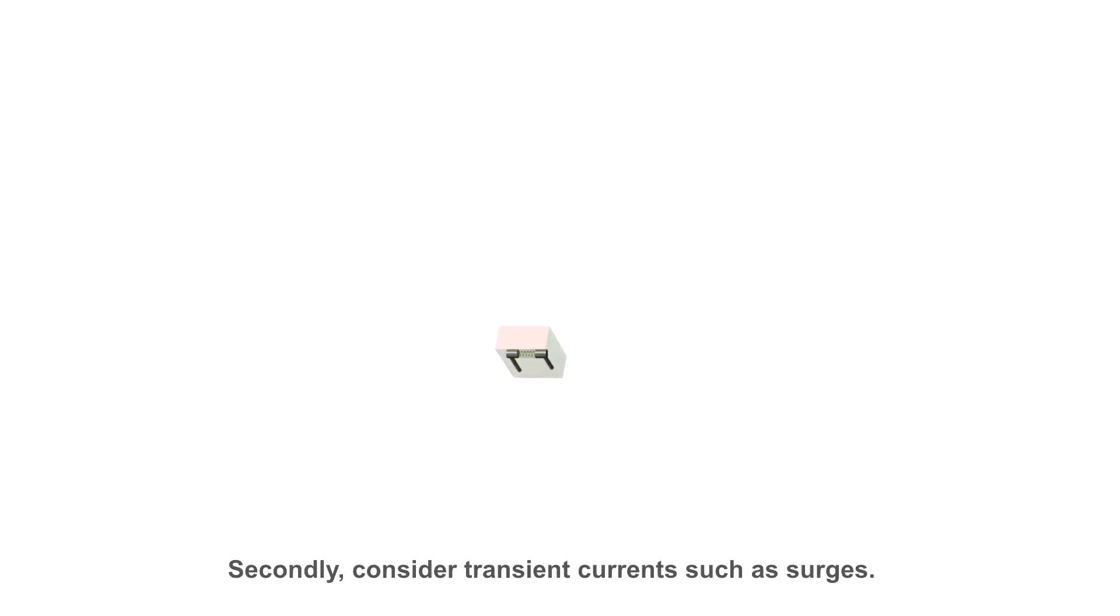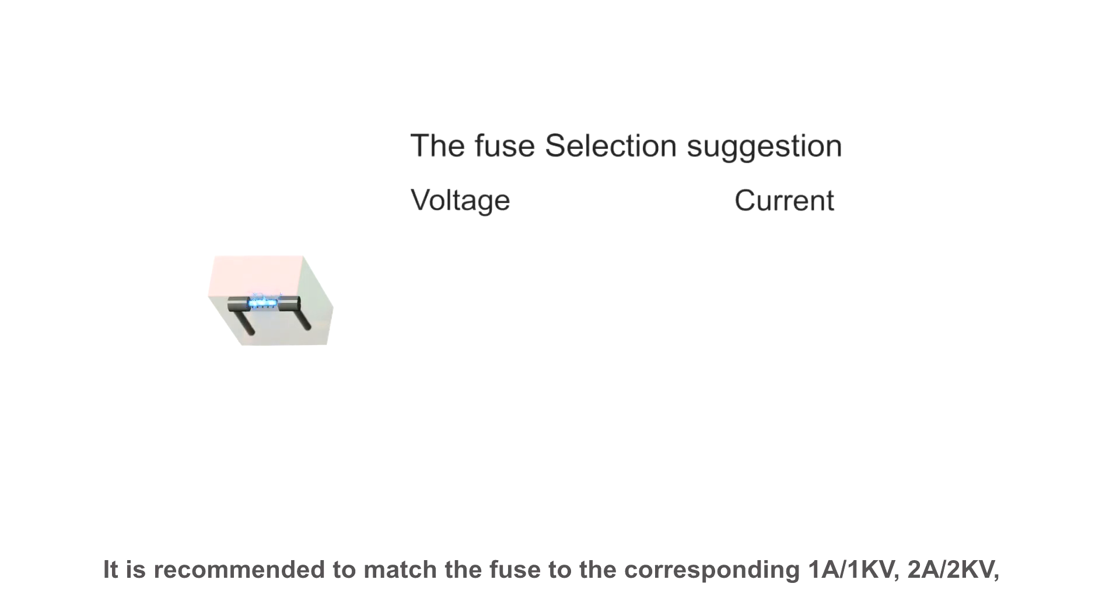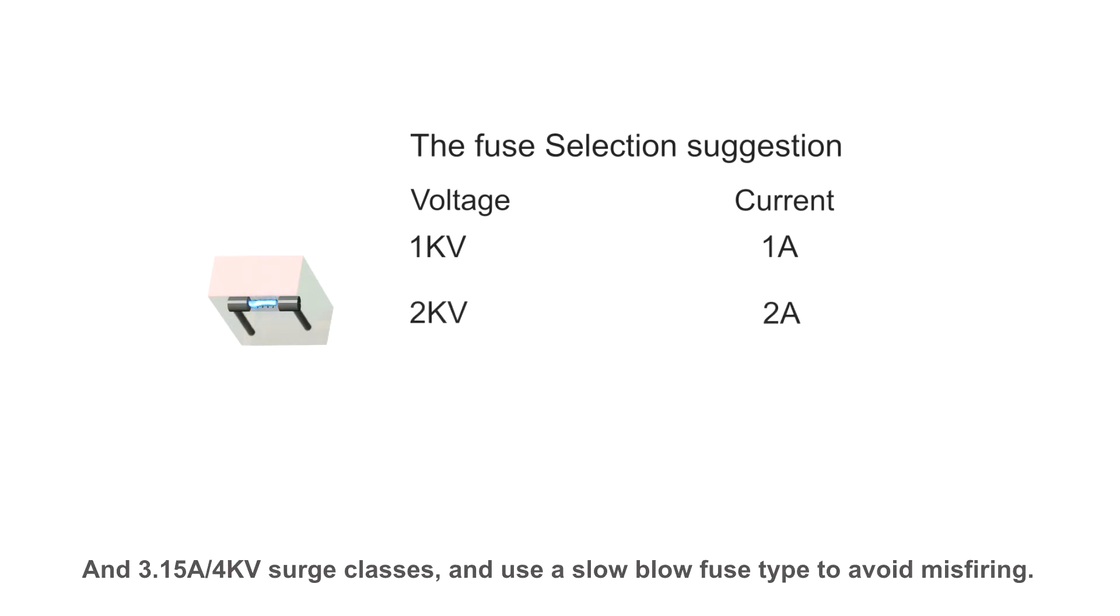Secondly, consider transient currents such as surges. It is recommended to match the fuse to the corresponding 1A 1KV, 2A 2KV, and 3.15A 4KV surge classes and use slow blow fuse to avoid misfiring.